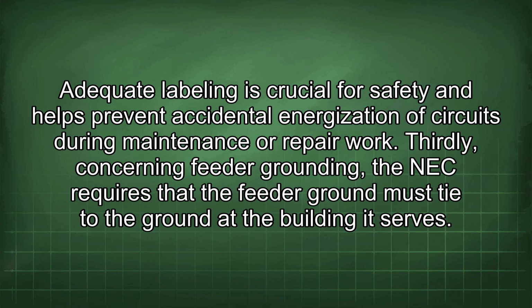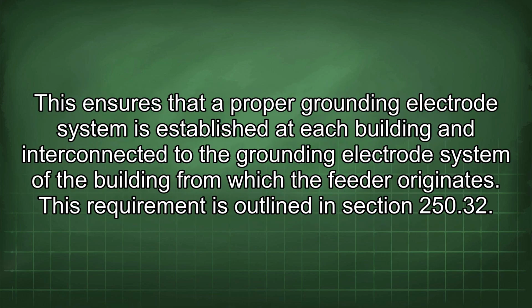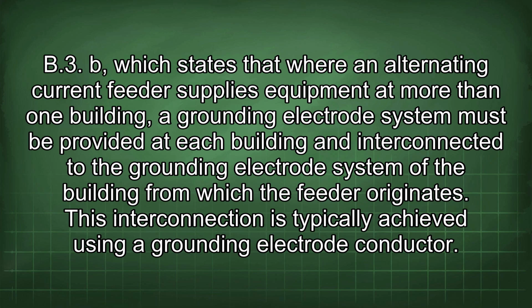Thirdly, concerning feeder grounding, the NEC requires that the feeder ground must tie to the ground at the building it serves. This ensures that a proper grounding electrode system is established at each building and interconnected to the grounding electrode system of the building from which the feeder originates. This requirement is outlined in section 250.32(B), which states that where an alternating current feeder supplies equipment at more than one building, a grounding electrode system must be provided at each building and interconnected to the grounding electrode system of the building from which the feeder originates. This interconnection is typically achieved using a grounding electrode conductor.